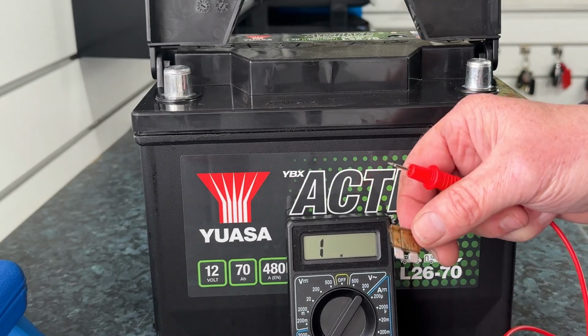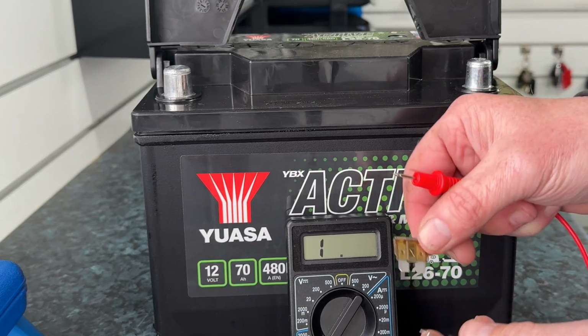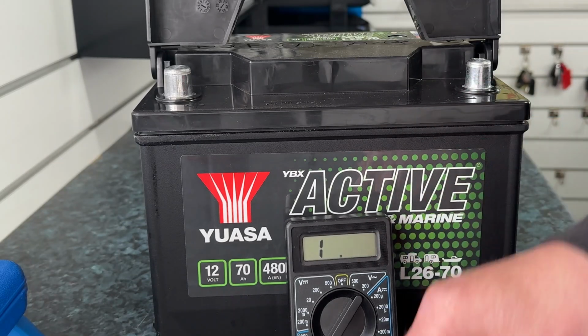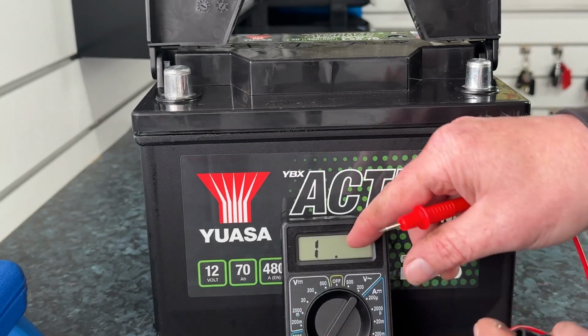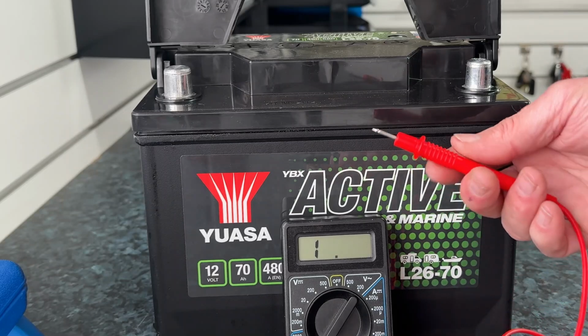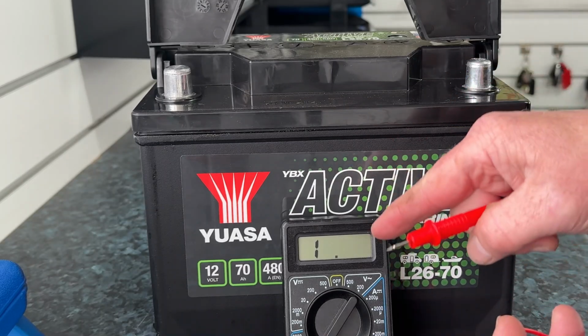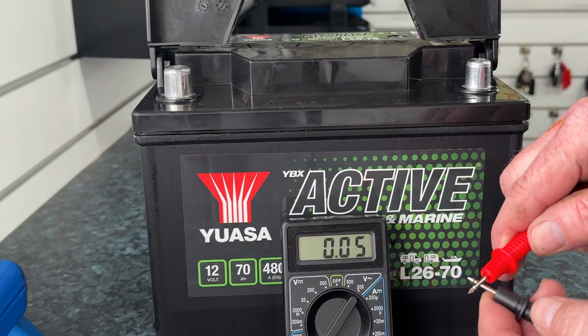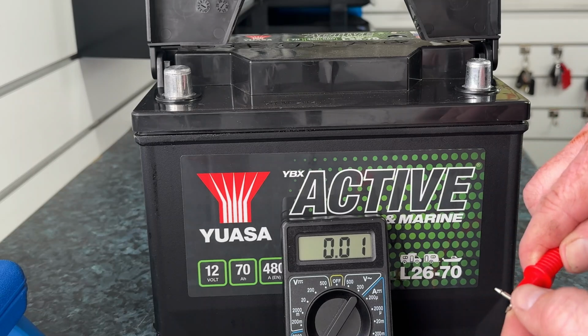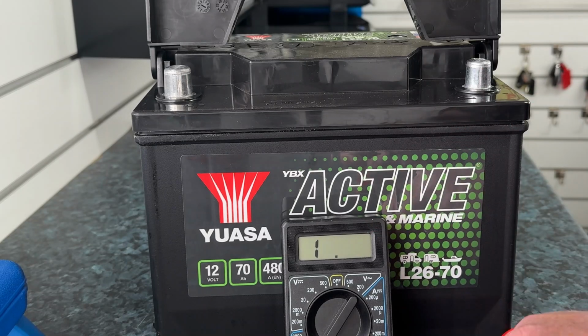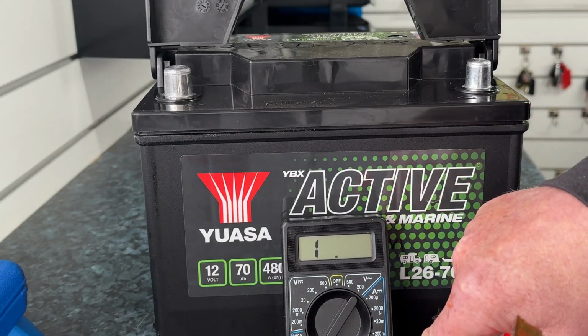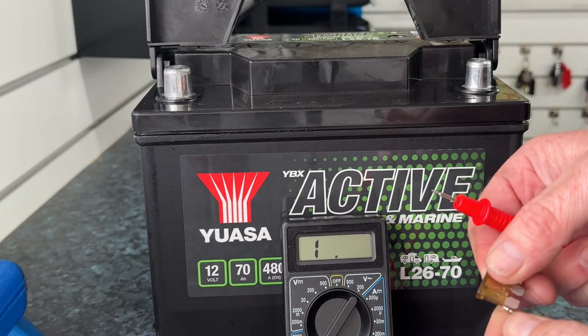So that means that fuse is okay. If that fuse had blown, then it wouldn't move, it would just stay on one, which means it's completely resistant because there's no way the power is getting through it. I always check to make sure the multimeter is working, just touch them two together to make sure the system's working before you test any fuses. Just make sure you haven't unplugged this or one of these isn't broken or anything like that.